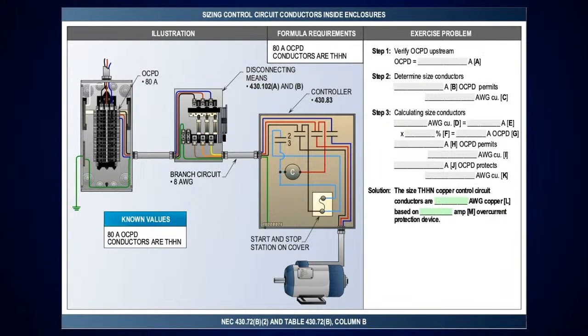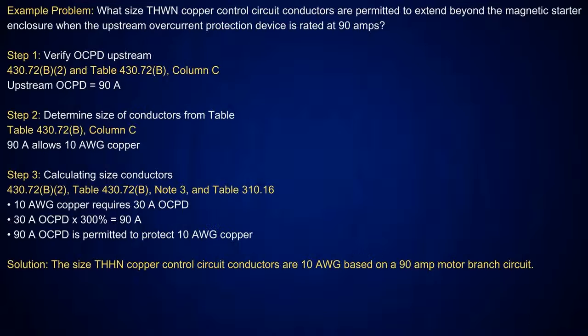So yeah, that's funny. But this one here's an 80 amp, and you're going to do the same thing. You're going to look at table 430.72B2 and then look at that note 3, and then you'll go get those amperages and then put that percentage on there to verify that table 430.72B works exactly as they say.